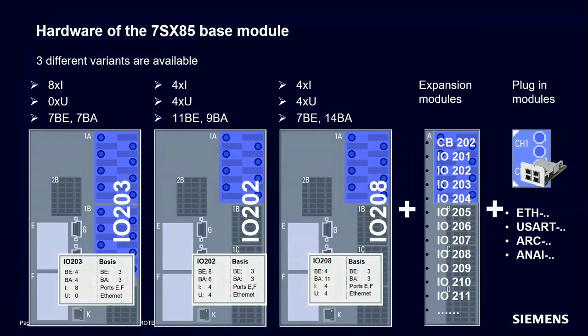Where the base module with the I/O 202 has more binary inputs, the other one containing an I/O 208 has more binary outputs. Of course, these base modules can be expanded with all the modules which are also available for the type-related Siprotec 5 devices. Finally, the base modules can be equipped with the same plug-in modules as for the type-related Siprotec 5 devices.